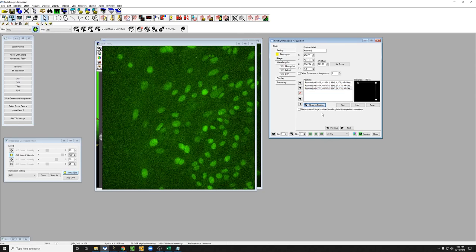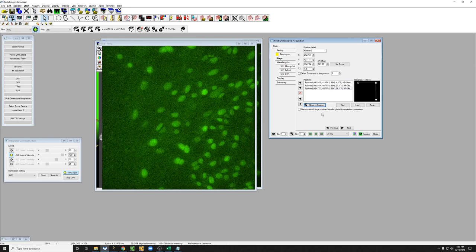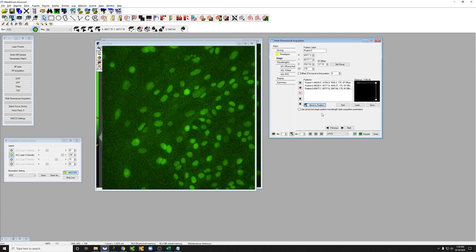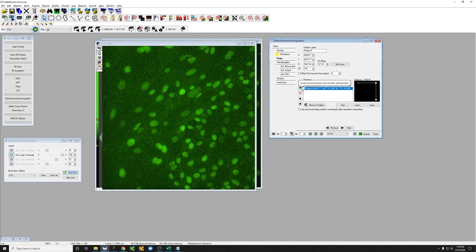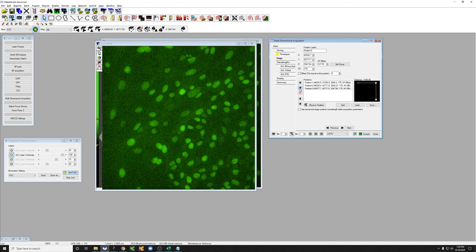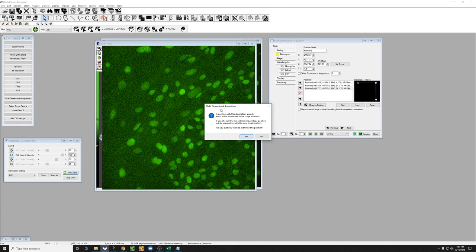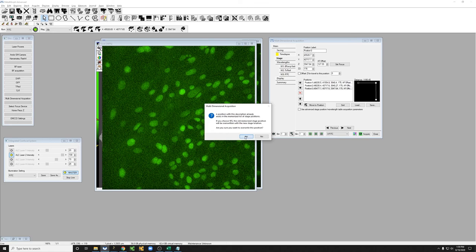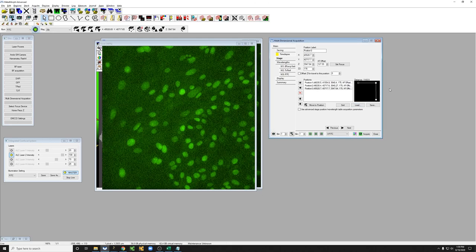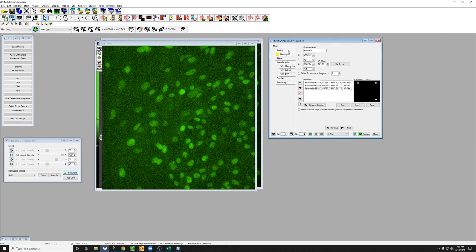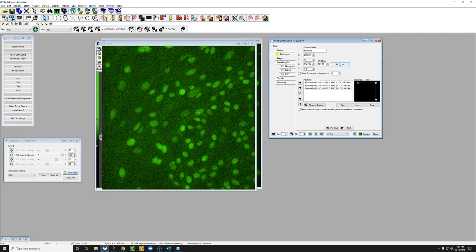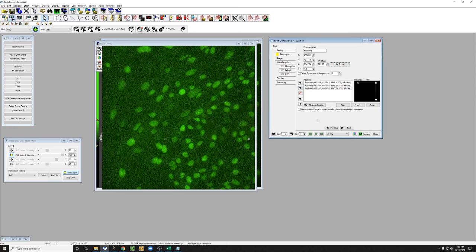If you want to modify a position, so let's say I actually want this position to be a little bit offset in X, Y, or maybe it was not in the right position in Z, I can then click on move it. So I've changed it a little bit. And then if I click on this button, because this says position three, it's going to try and overwrite it. It gives me a warning. But if I say yes, it will overwrite this position with the current setting. So whenever you do that, be careful, make sure you hit the set focus button to make sure that you have the right autofocus for this position. All right. So in this case, I would do that and then hit this button to overwrite it.